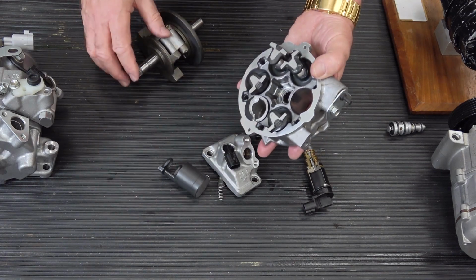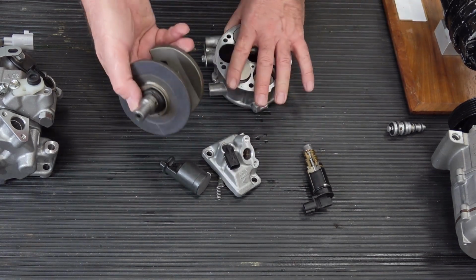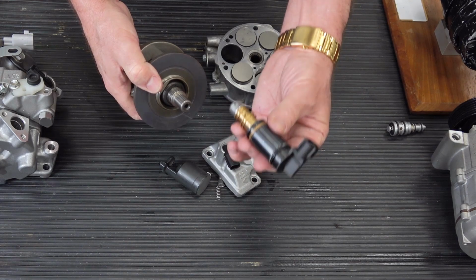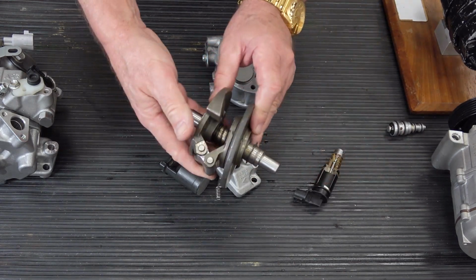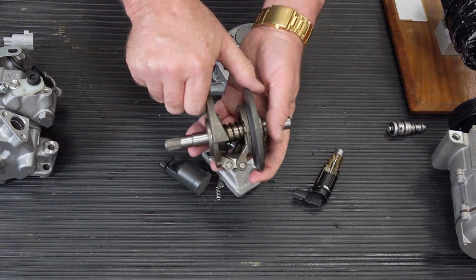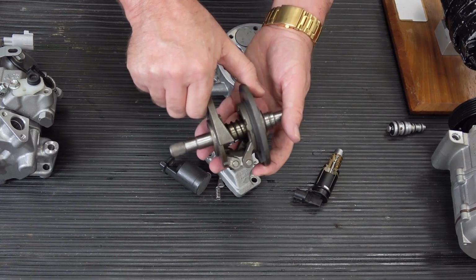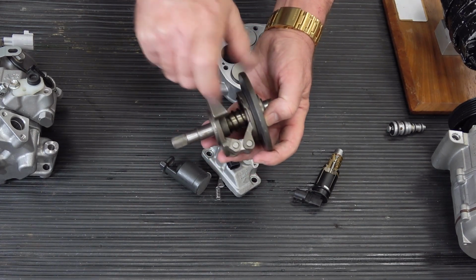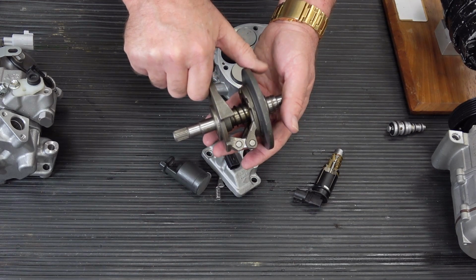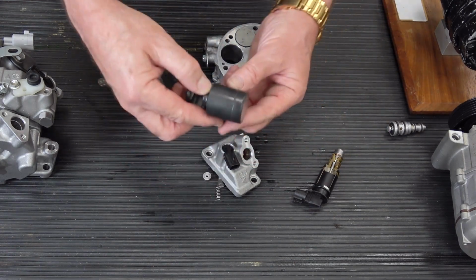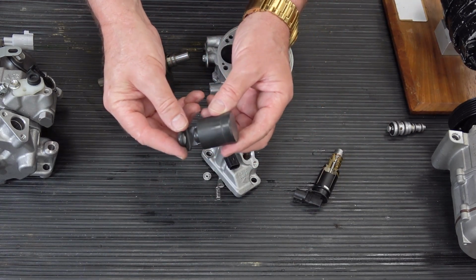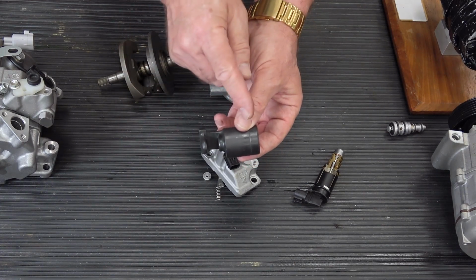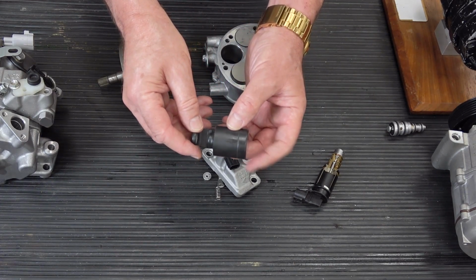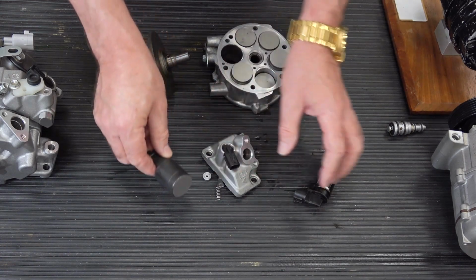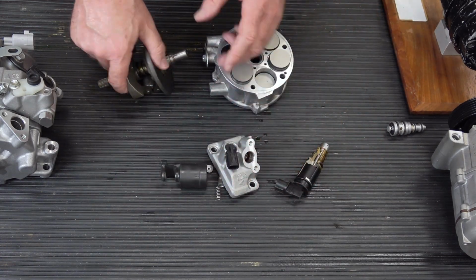They're very light. As the duty cycle changes to this solenoid, this is the actual swash plate from a later design compressor. You can see it's double hinged here. By changing the angle of that swash plate, I can change how far these pistons are dragged back and forth to control the stroke, and therefore the pumping displacement of the compressor. So that is ECV compressors.